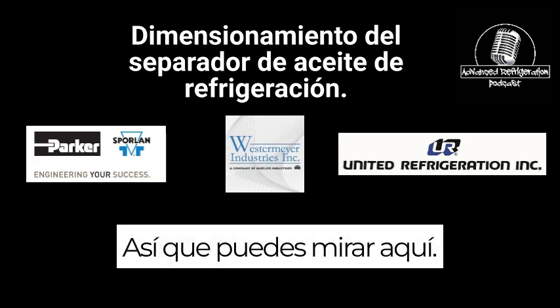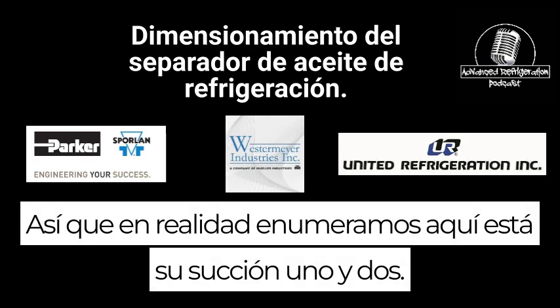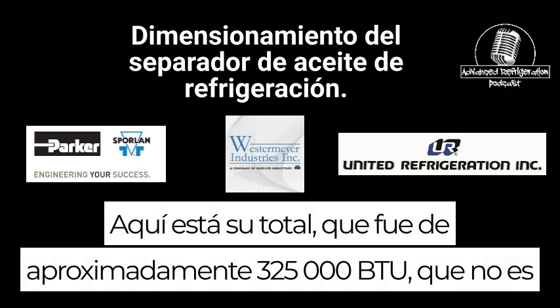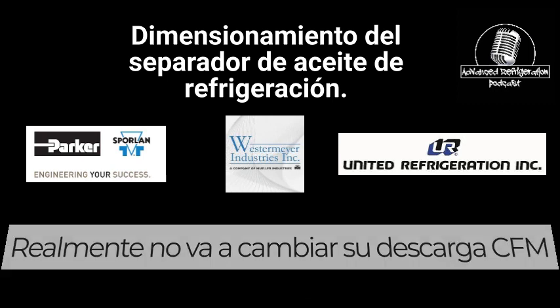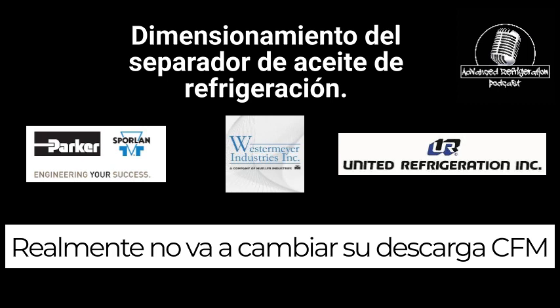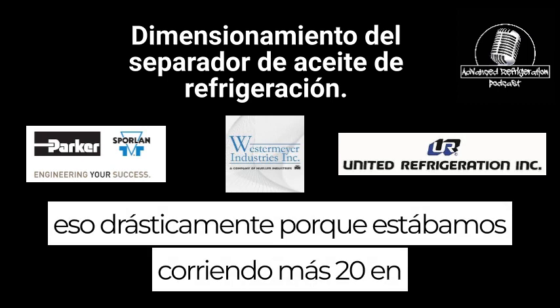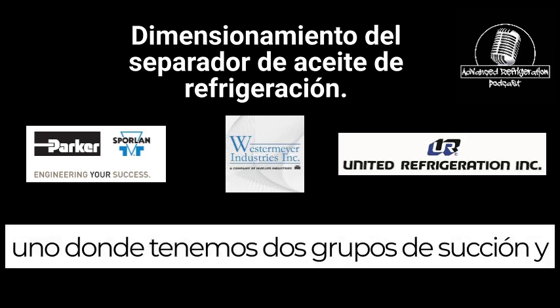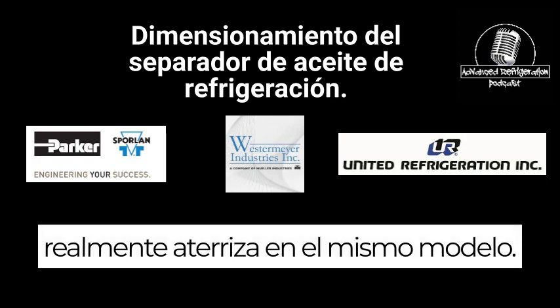So you can look here. We actually list, here's your suction 1 and 2. Here's your total, which was about 325,000 BTUs, which is not far off of what we just did on the other one. It's really not going to change your discharge CFM that drastically because we were running plus 20 on one where we got two suction groups, and it really lands on the same model.